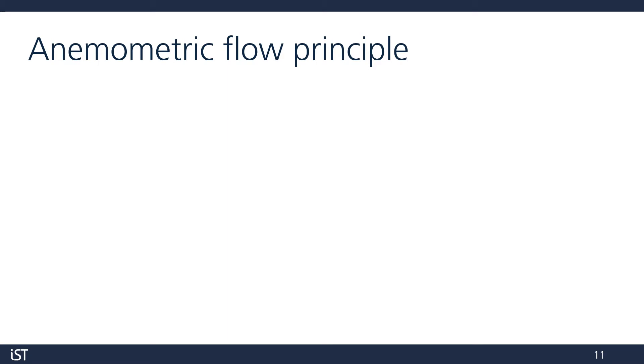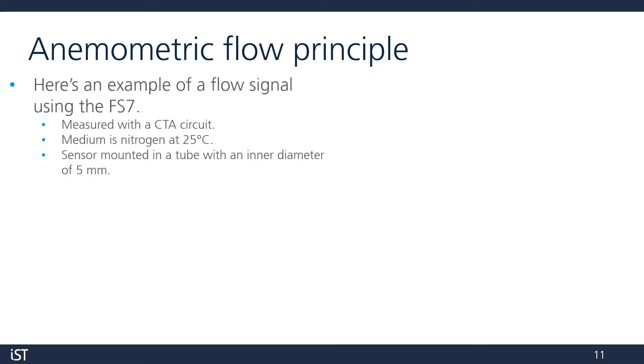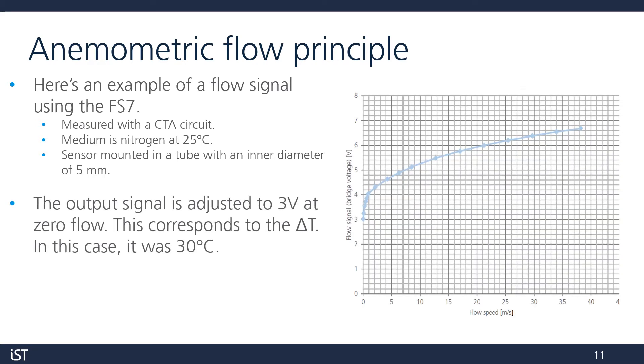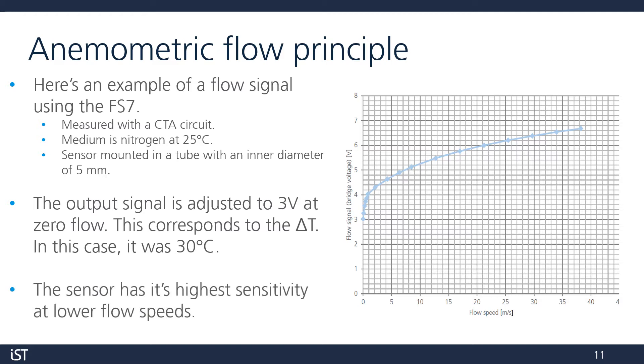Let's take an example of a flow signal using an FS7 mounted in a 5 mm diameter tube. The medium is nitrogen at 25°C, and our temperature difference is set to 30°C. We perform the measurement using a CTA circuit. The output signal is adjusted to 3 volts at zero flow, corresponding to our temperature difference of 30°C. As you can see by the slope, the sensor has its highest sensitivity at lower flow speeds.